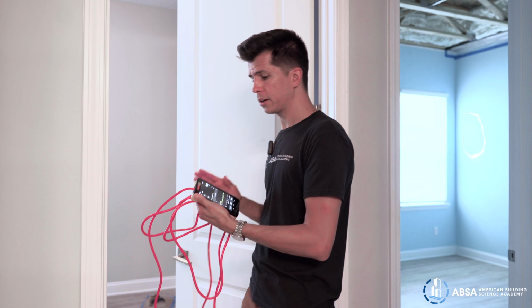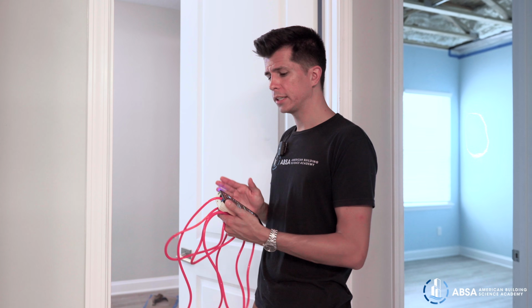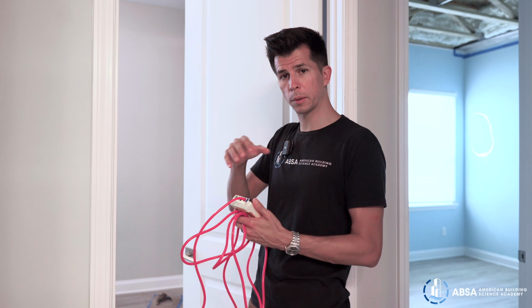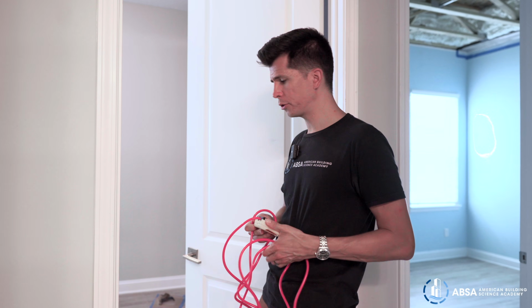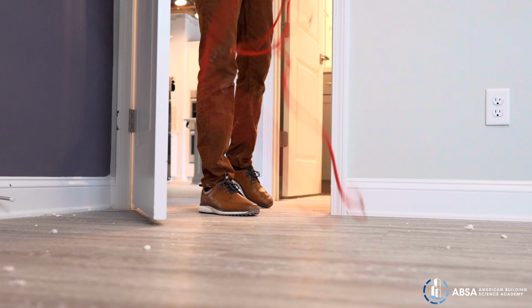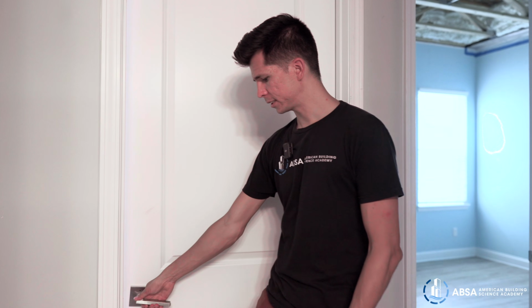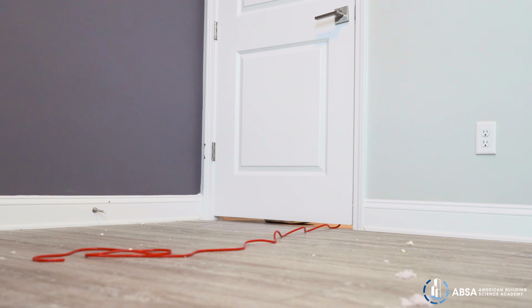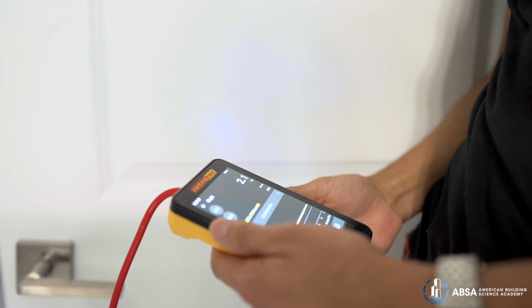So what I'm checking is the pressure differences between the hallway and the room. I'm going to do that with a manometer. This manometer is going to measure the pressure in the area where I'm standing. And I'm going to throw this tube under the door and close it. What that's going to do is tell me what the pressure differences are between these two areas. So current code allows a pressure difference of plus or minus 2.5 pascals. Right now we're sitting around 2 pascals. So that's not enough of a pressure difference to be concerned about. It's not enough restriction to cause circulation problems. So I think this room's going to check out. I'm going to check the rest of them and then we're going to see what Reagan's up to.